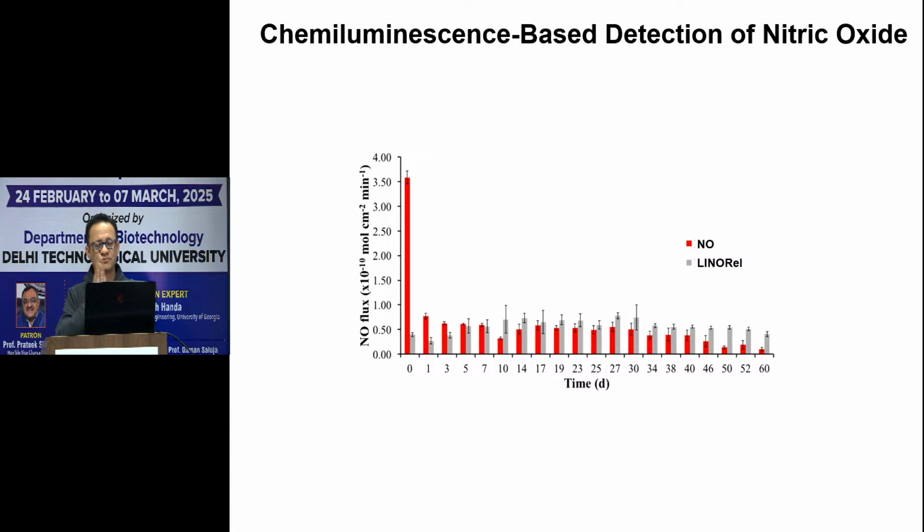But you can also imagine how we would be thinking when we were designing this surface, right? The question is, do we make the NO releasing surface first and then add slipperiness to it, or do we make the slippery surface first and then make it NO releasing? So all this is more optimization. The beauty of a slippery surface is you can just swell silicone oil into the walls, just like we can swell NO donor into the walls. We talked about how you can make a solution of NO donor, put your polymer in it overnight, it swells inside, and then you let the solvent dry. Similarly, silicone oil can go into the walls, and then it very slowly keeps replenishing on the surface, so your surface stays slippery.